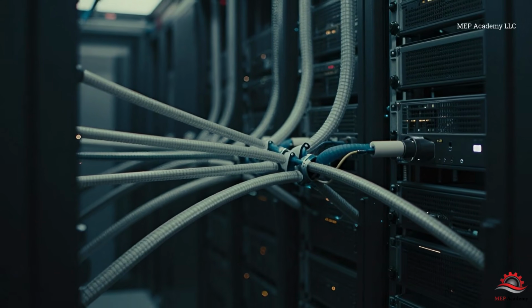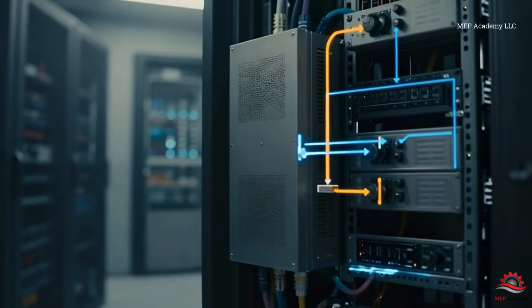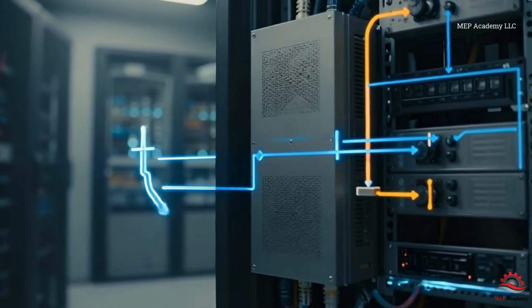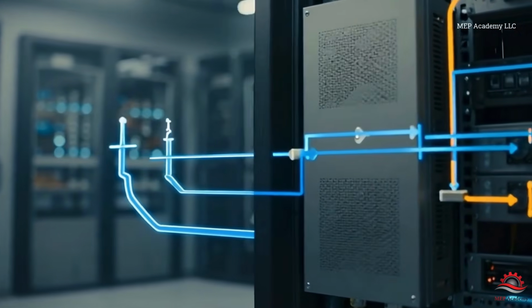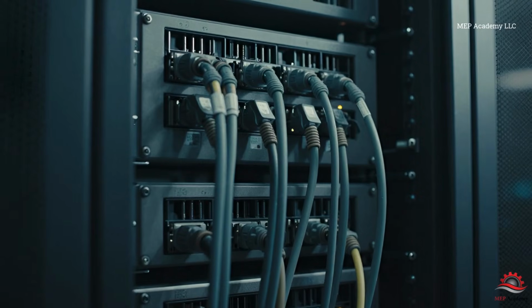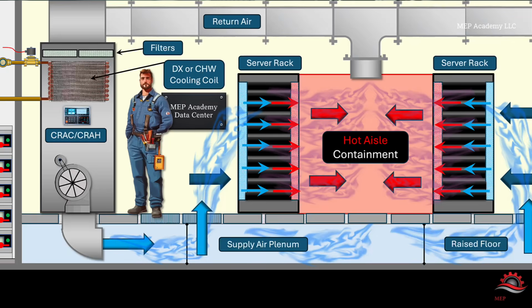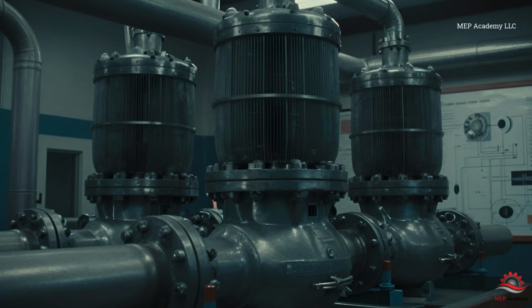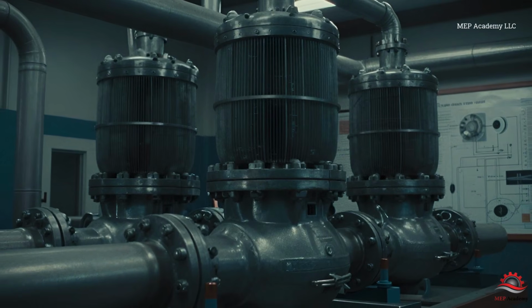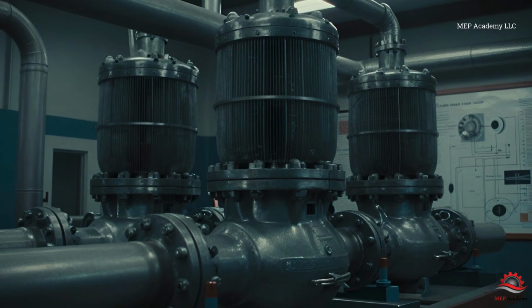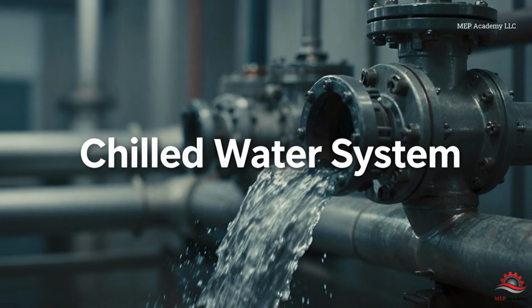covered in this series. If you've been following this series, you already understand how power flows from the utility grid, through UPS systems, and into the server racks. You've also seen how airflow is managed using hot aisle and cold aisle containment. Now we're going one level deeper. Because behind all that airflow is a mechanical system doing the real work of removing heat. That system is the chilled water system.